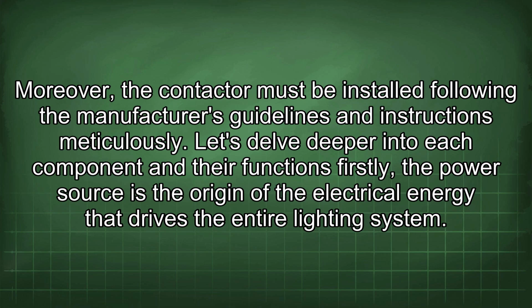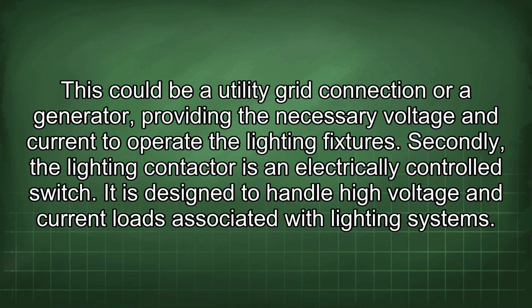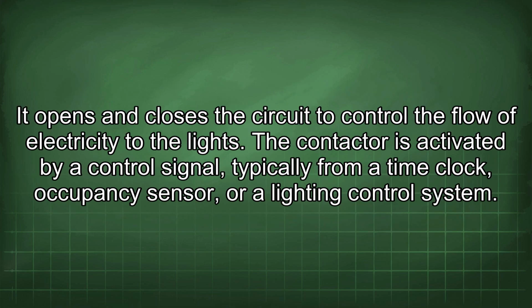Firstly, the power source is the origin of the electrical energy that drives the entire lighting system. This could be a utility grid connection or a generator, providing the necessary voltage and current to operate the lighting fixtures. Secondly, the lighting contactor is an electrically controlled switch. It is designed to handle high voltage and current loads associated with lighting systems. It opens and closes the circuit to control the flow of electricity to the lights. The contactor is activated by a control signal, typically from a time clock, occupancy sensor, or a lighting control system.